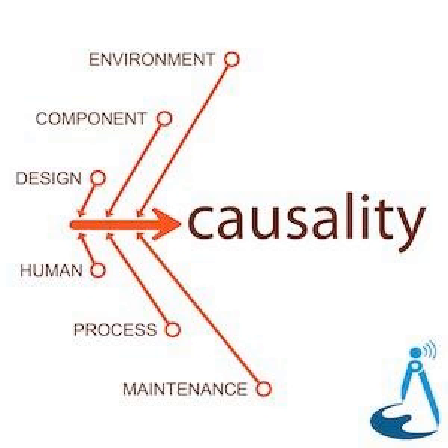However, in this particular case, all 6 of the high-voltage transmission lines that connected the power plant to the electrical grid were destroyed by the earthquake, and the following tsunami, I should say. Now, the so-called essential service water systems that keep the cooling water circulating through the reactor have several other backups. The backup system installed on site at Fukushima had an independent, redundant power system of diesel generators. The generators were regularly tested to ensure they operated when they had to. Their fuel was topped up, everything was maintained. They were, so far as we are aware anyhow, in full working order. When the scram event occurred, the diesel generators were fully functional, even when they lost mains power.